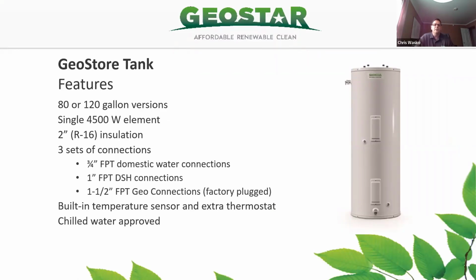We also have a geo storage tank, 80 to 120 gallon version. It has a single 4,500 watt element available in it. You can also order a secondary one if you need to at an installation point. It comes with all of the connections you're going to need. It's piped in and it's able to go right off the bat. It has built-in temperature sensors and extra thermostats as well. The unit is chilled water approved.